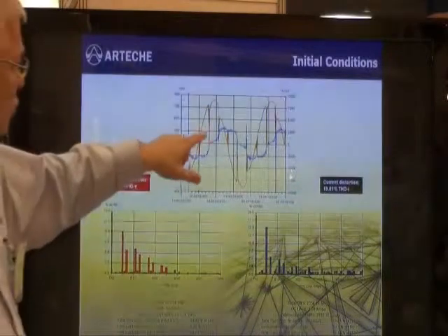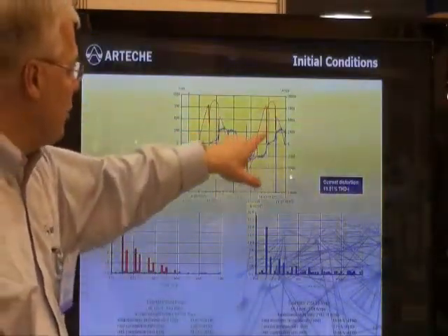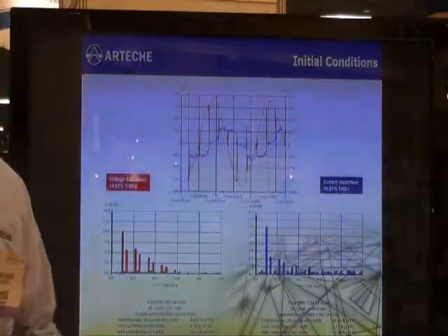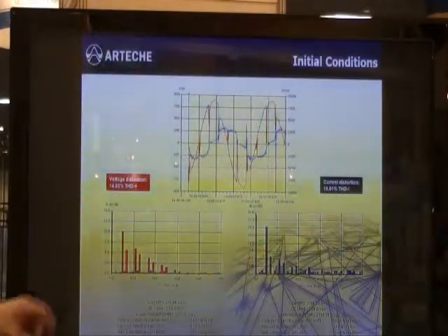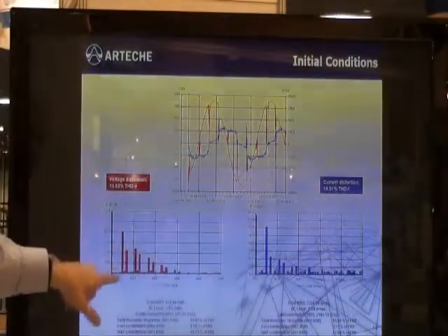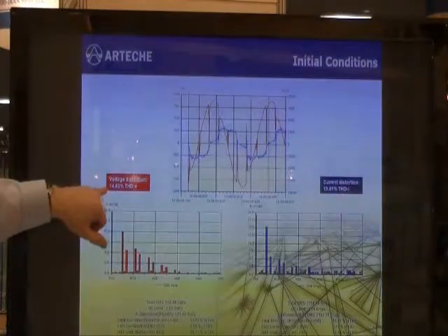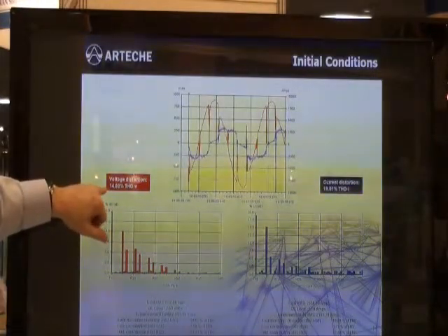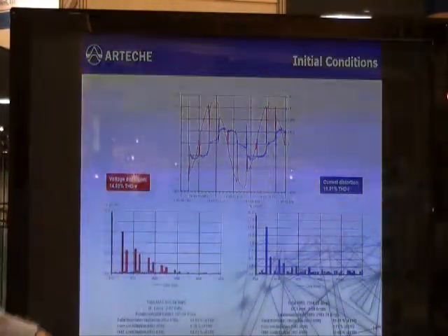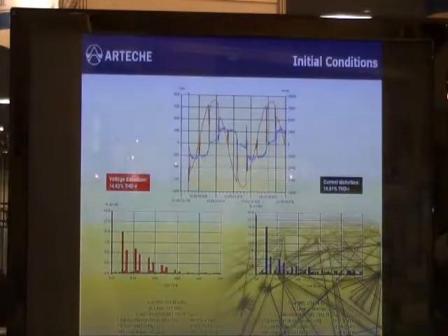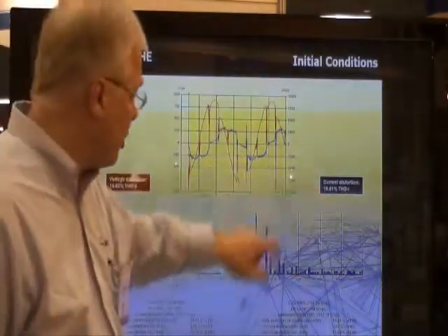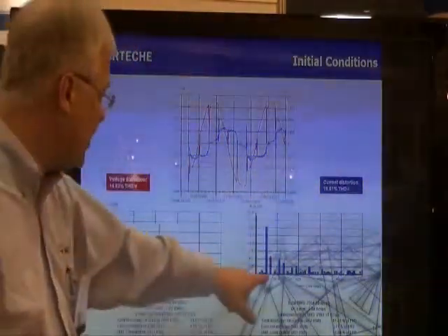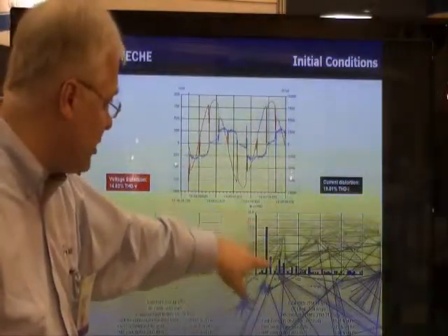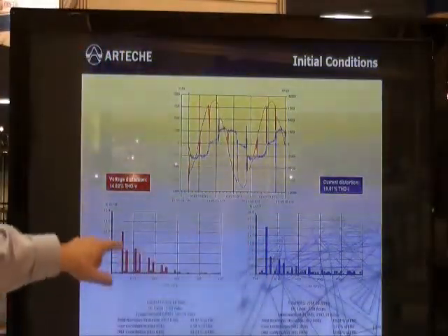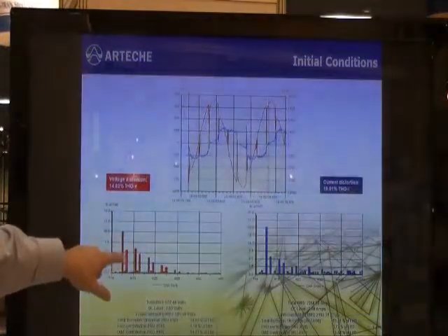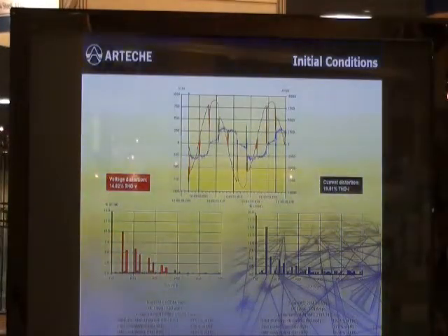So the initial conditions were this voltage waveform, in red, with the very high potential notches. And here we see the voltage distortion with about 14.8% total harmonic voltage distortion on the system. The objective again was 5%. The current distortion here is 19%, and we see that the 5th harmonic is the richest with the 7th being next, and again the 5th and 7th are the 2 richest harmonics in the system.